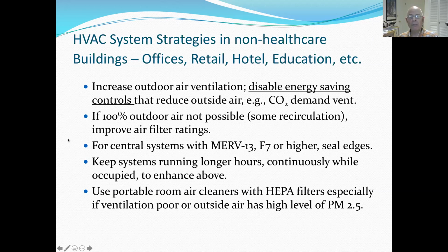For central systems with any kind of pressure ability, I've yet to find a system that cannot handle a MERV 13 filter, and usually you can go higher. Sometimes people worry, I can't upgrade my filtration because I don't know if it can handle the pressure drop. I have yet to see a system, by calculation or by observation, that can't handle at least MERV 13. Now those little split systems, those mini splits, they can't. But a central system with a 1-inch filter drop, I believe they can all handle it.